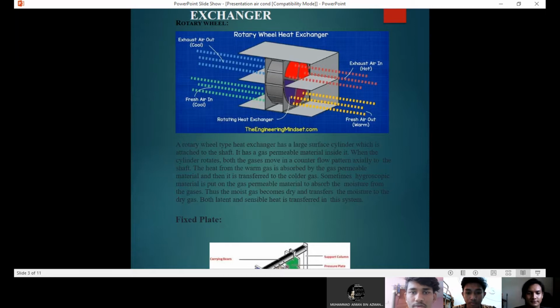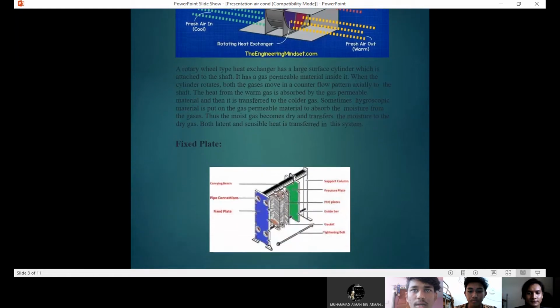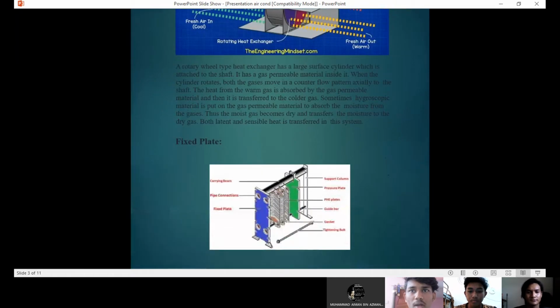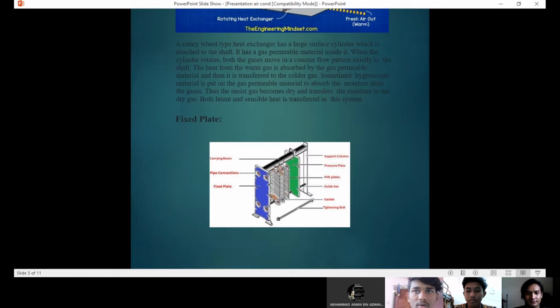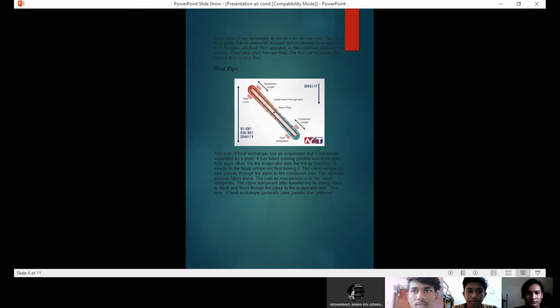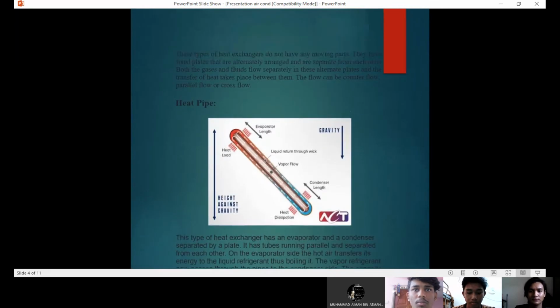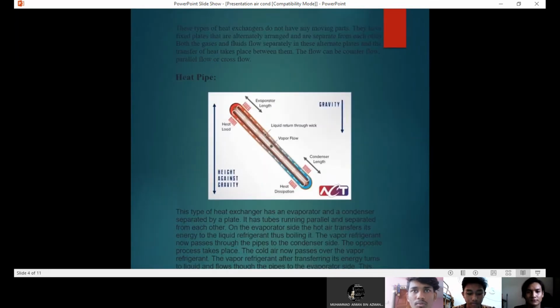And following, the fixed plate. This type of heat exchanger does not have any moving parts. It has fixed plates that are alternately arranged and separated from each other. Both the gases and fluids flow separately in these alternate plates and the transfer of heat takes place between them. The flow can be counterflow, parallel flow, or cross flow.